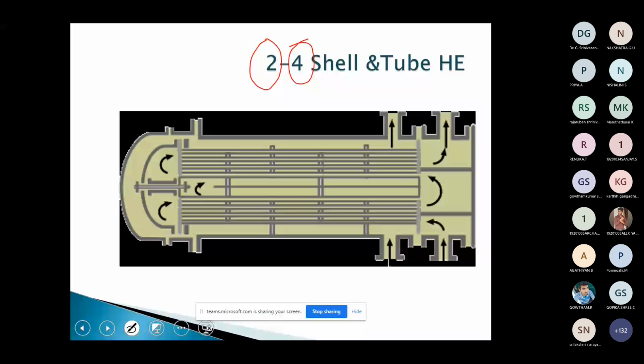So this 2-4 shell and tube heat exchanger is widely used. You can see 2 means shell side and 4 means tube side passages. From this diagram, you can see the number of passages for tube side is 4. Fluid enters here, this is 1, 2, 3, 4. So it flows 4 times, whereas on the shell side, this fluid comes here, goes here, and then goes here. So only 2 passages. 2 passages on the shell side, 4 passages on the tube side.